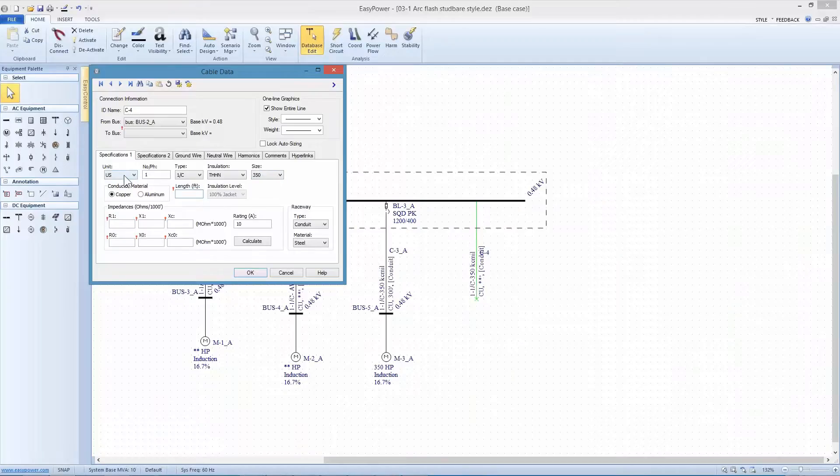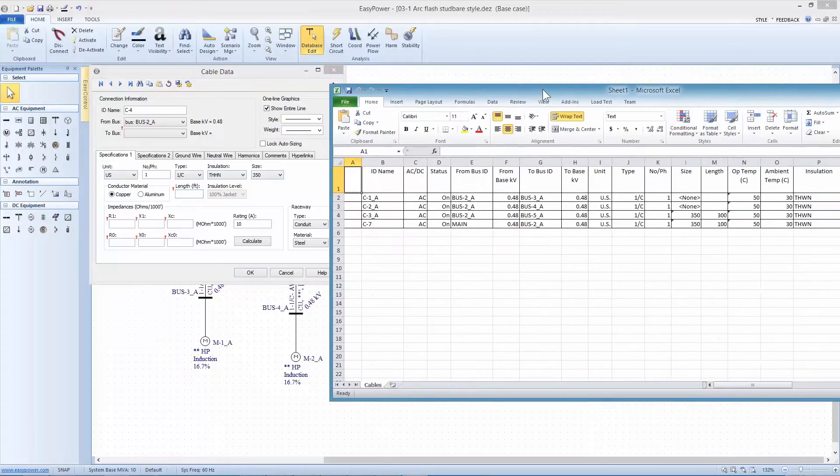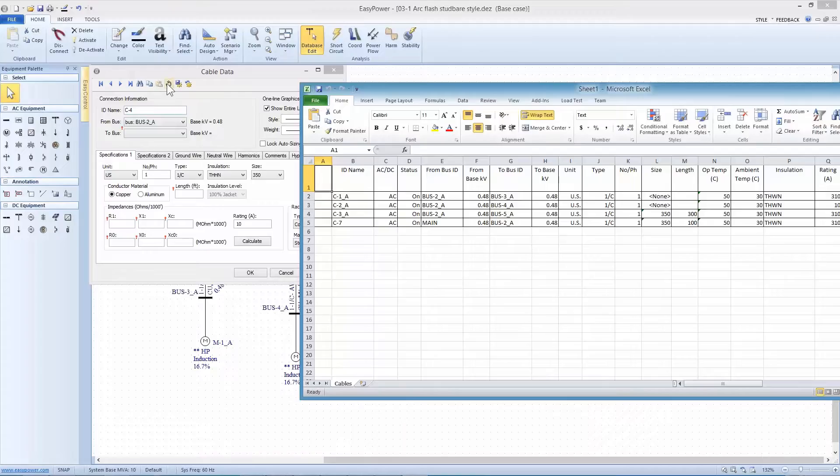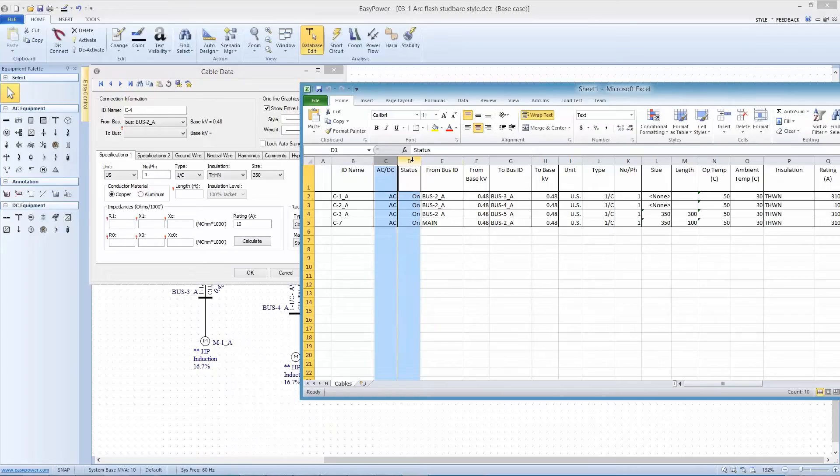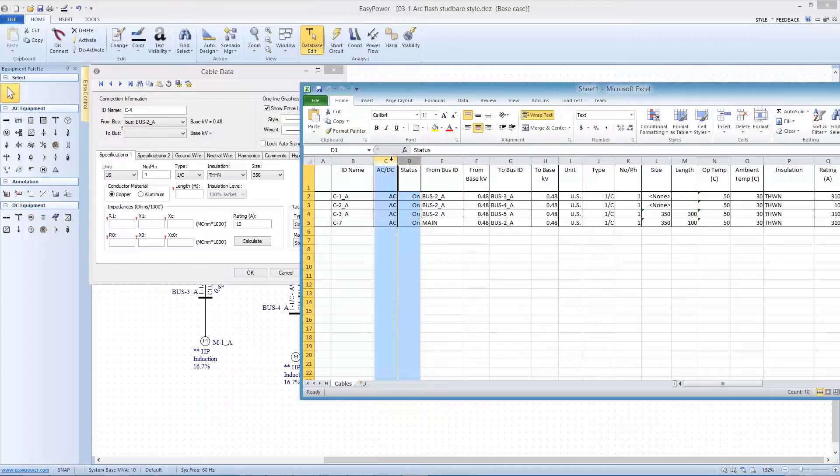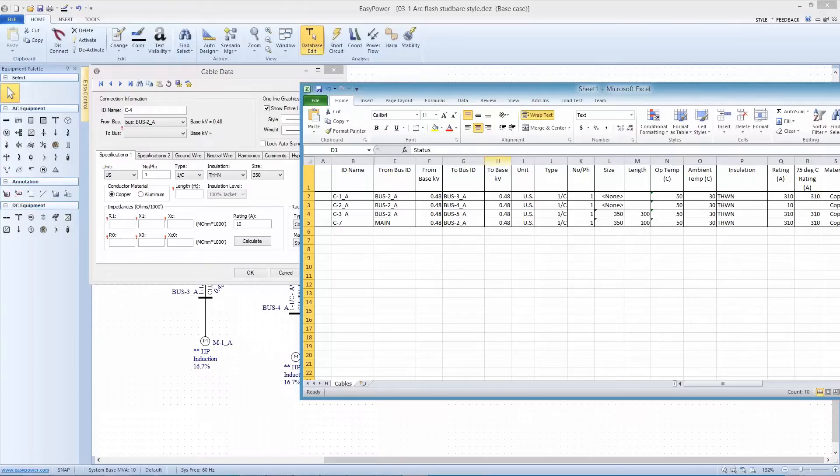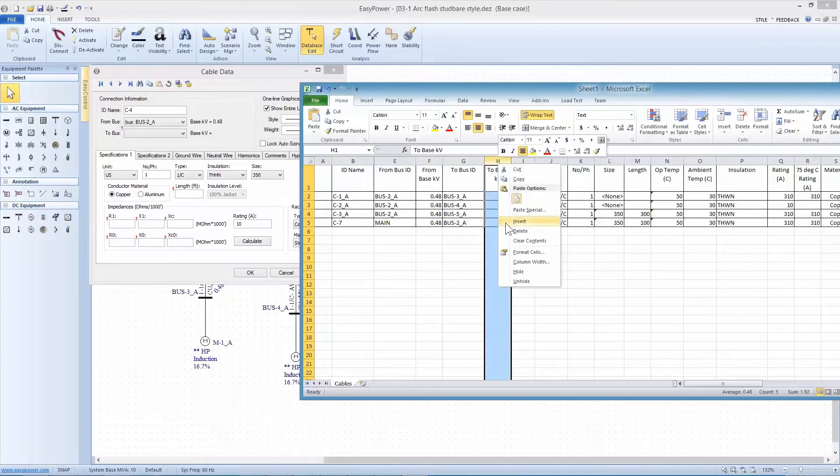So the most important elements end up being the number of conductors per phase, type of cable, the installation, the size, and the length. If I come back over here to my spreadsheet, clearly I need to know what the ID name is. That's something else we need to spend some time thinking through, because the naming convention ends up being an important part of our organization. Once I get beyond that, I'm assuming all of my cables are AC, so I don't necessarily have to enter data there. I wouldn't be taking data if the circuit's not on. Something your system may require some of these columns that I'm going to take out, but I'm going to hide these as I go through to minimize the number of columns I'm looking at. Making a note for the bus the cable starts and where it ends, and a note on what the voltage is. If everything's 480, I can take this out. I don't have to care about units because for now I'm using everything in US.